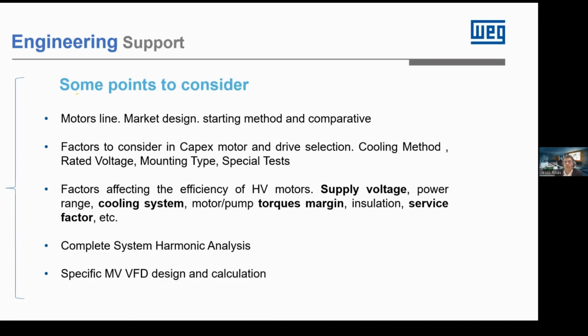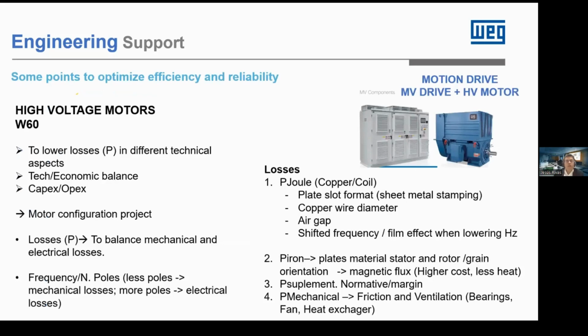This means that you are not going to have only one point. Nowadays, we are looking for several points in the curve of the pump and the curve of the motor that have to be guaranteed. If we go into details, when we have to select the high voltage motors for a desalination plant for the RO process, typically our model is the W60 model, which is the most used, but there are some other types depending on the size. W60 for the RO plants, the high pressure pump, their power ranges from 1 to 7 megawatts. Let's say normally now in bigger plants, we are talking about 6 megawatts for the high pressure pump, and for the feed low pressure pump is 2, 1, 1.5, something like that.